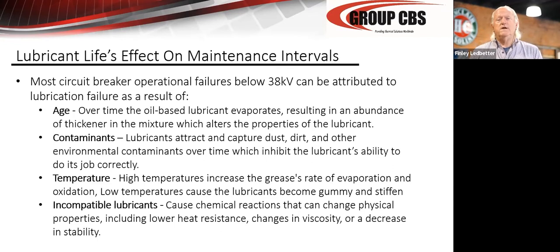If not, take a popsicle stick, take a sample, and make sure it's analyzed and they use the same lube. The alternative to that is to clean all the lube out and start with something you know and convert all your breakers to a modern lubricant that's available. I know that's harder, it's hard work, but it has to be done, okay?